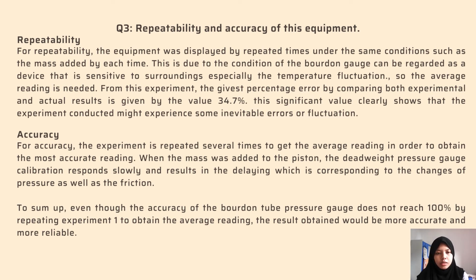So question 3 is about the repeatability and accuracy of this equipment. For repeatability, the equipment was tested repeated times under the same condition, such as the mass added each time. This is because the Bourdon gauge can be regarded as a device that is sensitive to the surroundings, especially temperature fluctuation. So the average reading is needed. From this experiment, the percentage error from comparing experimental and actual results is 34.7%. This significant value clearly shows that the experiment might experience some inevitable errors or fluctuation.